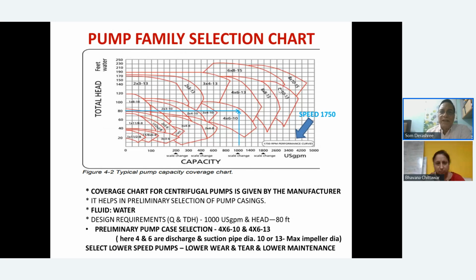Now let's come to the family of selection chart. Once you have arrived at a specific speed, you know the flow, you know the pressure. You have to tell the manufacturer, okay, please give me the curves. Let's say you have preferred a low speed curve, basically. This is the 1750 speed curve that has been given by the manufacturer. Of course, this is all US slides, so that's why you're seeing 1750 or 1800 as the curve, because 60 hertz is their frequency.